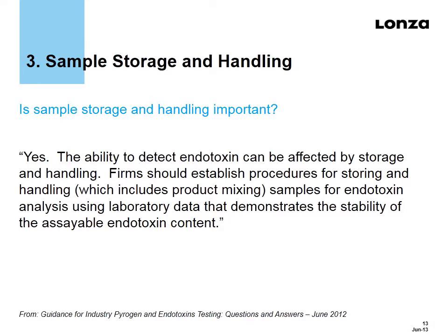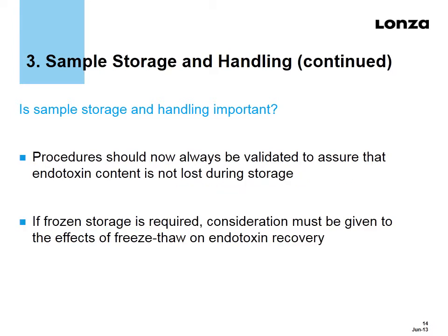The next question is regarding sampling, storage, and handling, and that is, are sampling, storage, and handling important? The guidance document says yes, the ability to detect endotoxin can be affected by storage and handling. Firms should establish procedures for storing and handling, which includes product mixing, samples for endotoxin analysis using laboratory data that demonstrates the stability of the assayable endotoxin content.